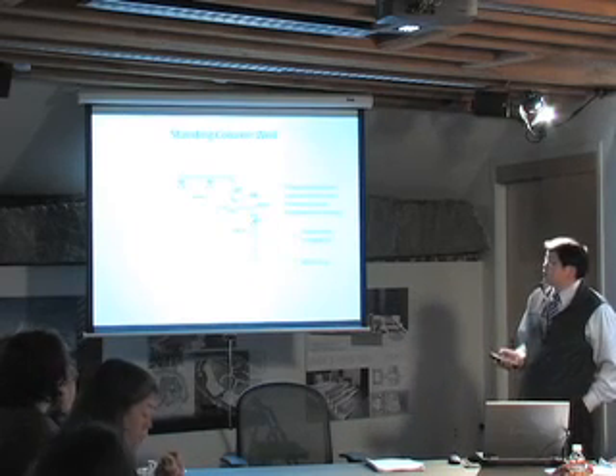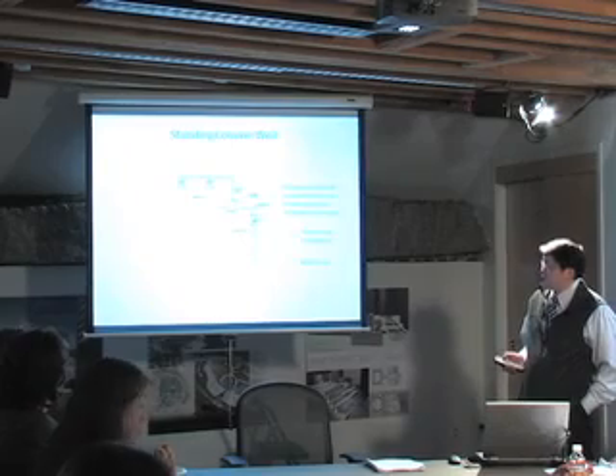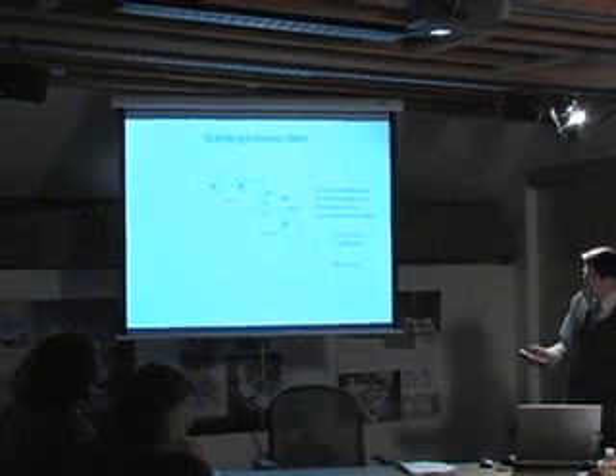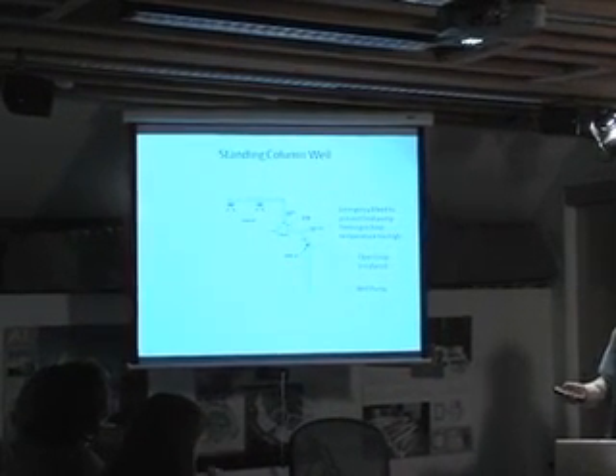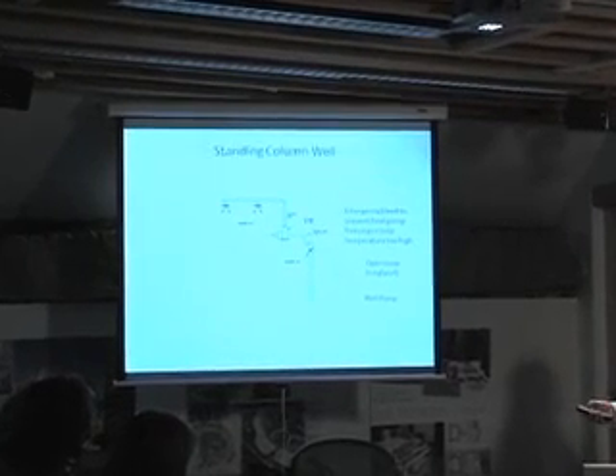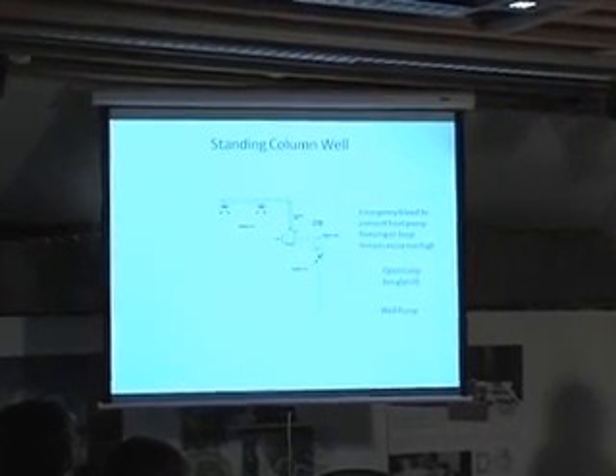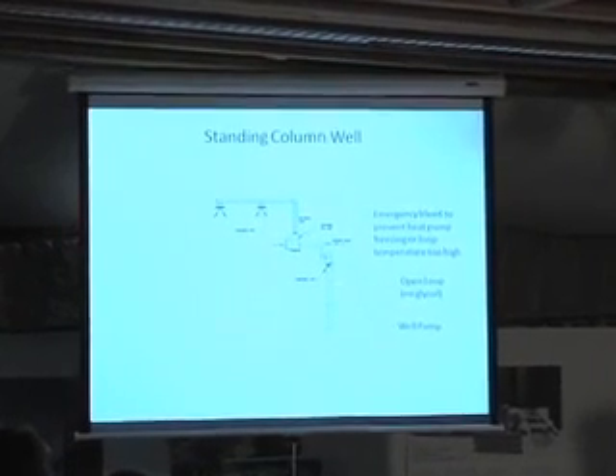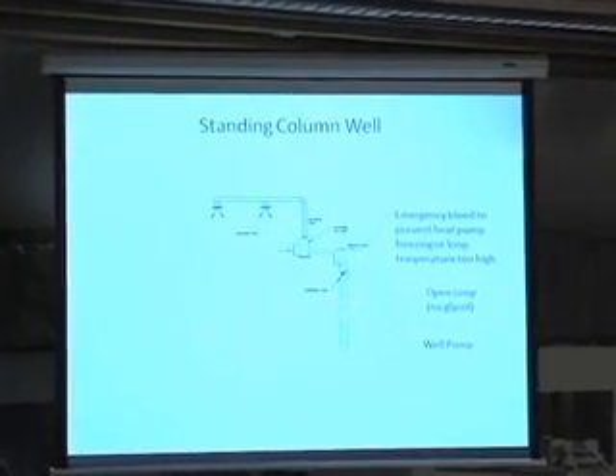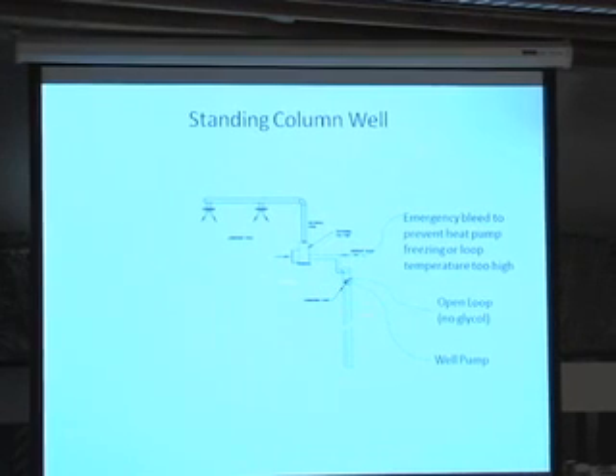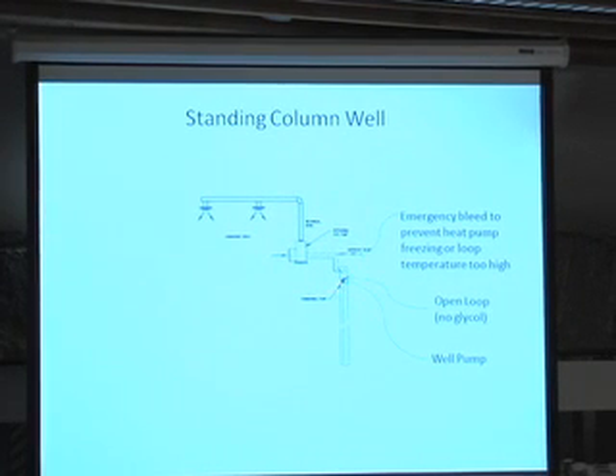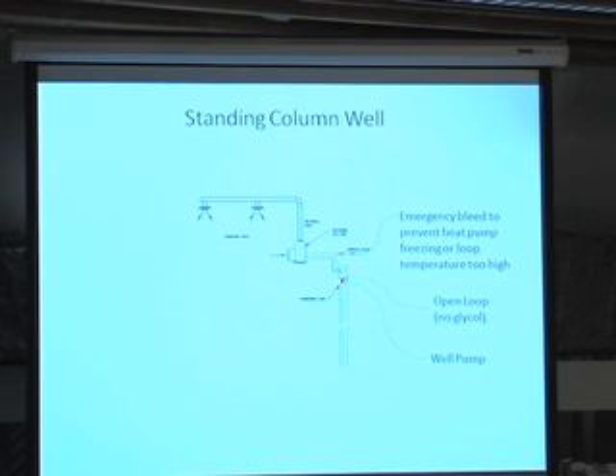Now this configuration is called standing column well. It's an open system. You also drill a borehole, usually 6-inch diameter or 8-inch. Can be very deep, 500 feet deep, 1,000 feet, or even 1,500 feet deep, sometimes 2,000 feet deep. And you drill so deep that you have groundwater in the well, it's a water well. And then you have a submersible well pump here, and a shroud pipe down to the bottom with holes in it.